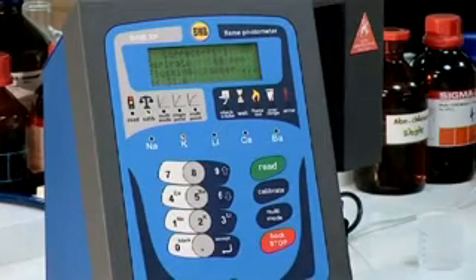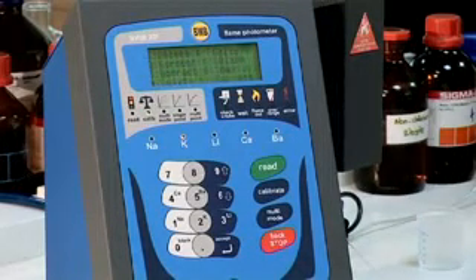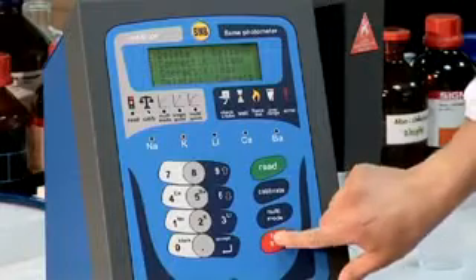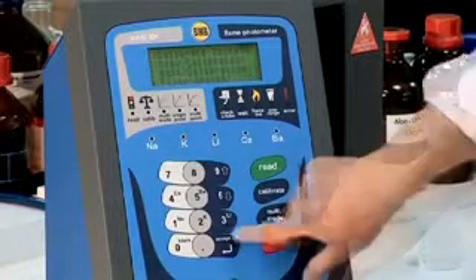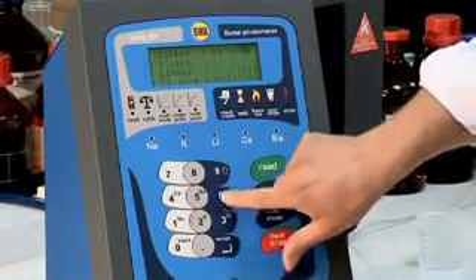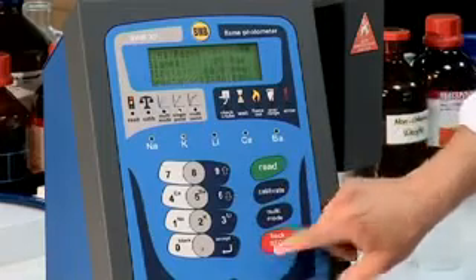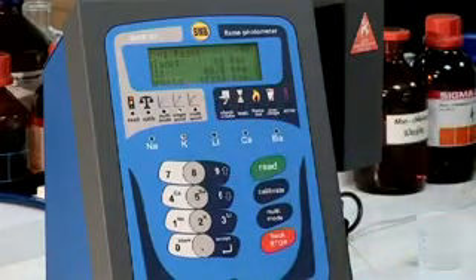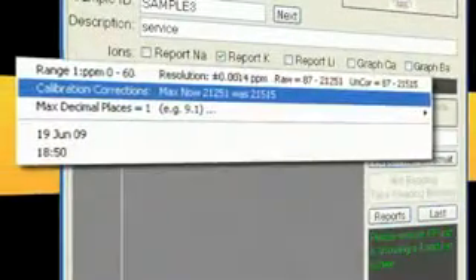An exciting feature of the Bwb Xp is the calibration correction. Flame photometers are known to drift over time due to temperature changes and flame setting changes, and as a result often need to be calibrated. The calibration correction will shift the entire curve to remedy the change. A multiple points curve can be corrected by aspirating just one solution, a real time saver.